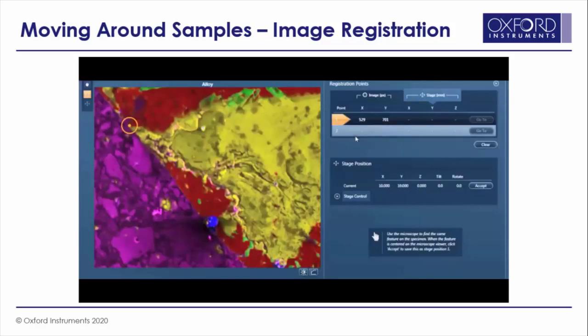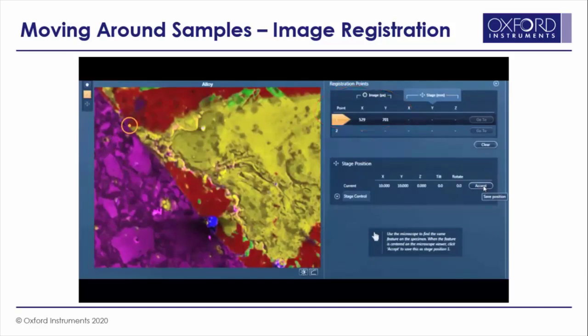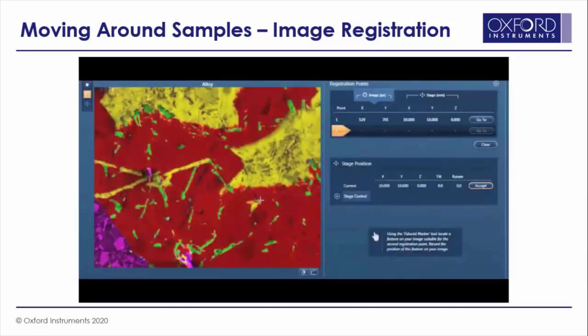The video shows the process of registering two points on a sample, and it is really quite straightforward. I've identified and marked a point in my image that I can easily locate in the SEM, and have brought that point to the centre of the field of view in the microscope. All I have to do then is click to make the association. I then go on to repeat the process for a second point, ideally a significant distance away. A good tip here is that if you're going to be using a sample for an extended period of time, you can save the locations of these points in the SEM's stage memory. You can then see me moving around the sample by double-clicking on the image, and navigation is both quick and intuitive. I always find that this approach really helps when working remotely, as the feedback within Aztec of where I am on the sample gives a lot of confidence, enabling me to work far more quickly and efficiently.